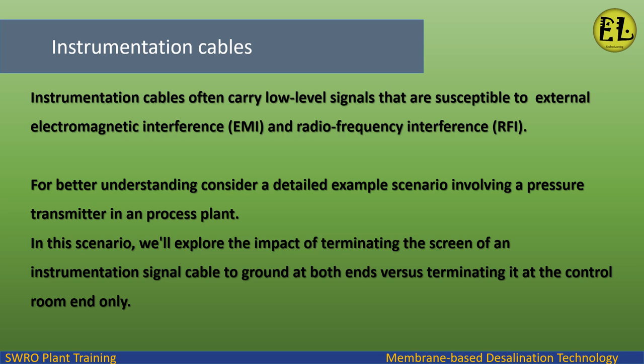Instrumentation cables often carry low-level signals that are susceptible to external electromagnetic interference (EMI) and radiofrequency interference (RFI). For better understanding, consider a detailed example scenario involving a pressure transmitter in a process plant, exploring the impact of terminating the screen at both ends versus terminating it at the control room end only.